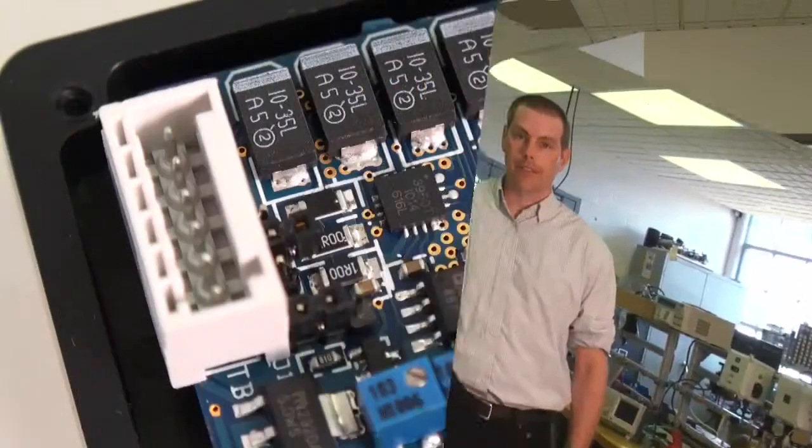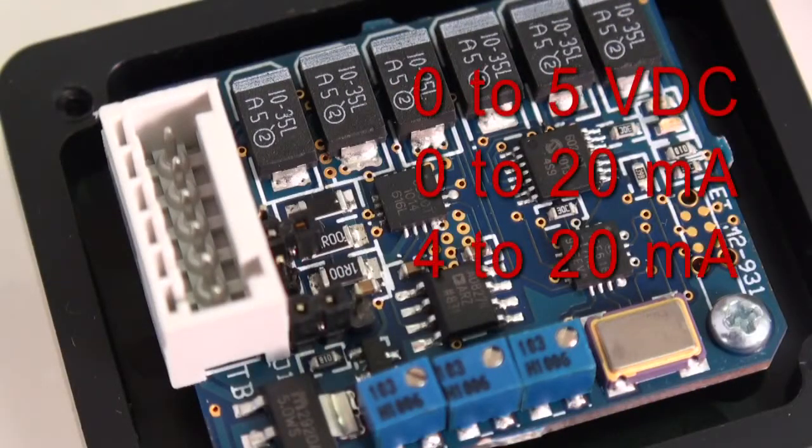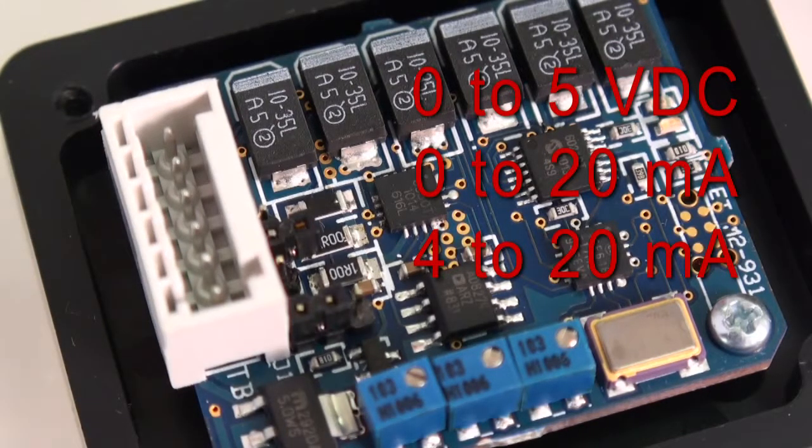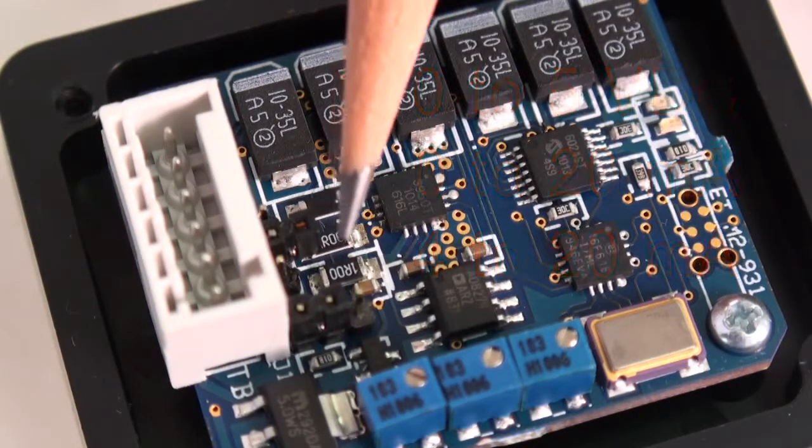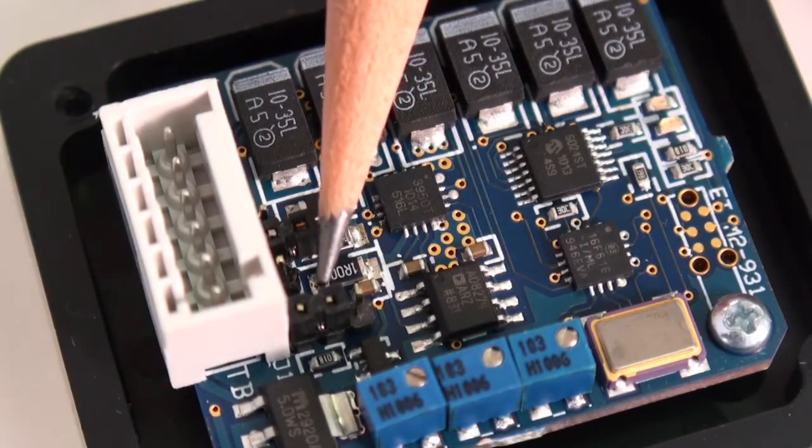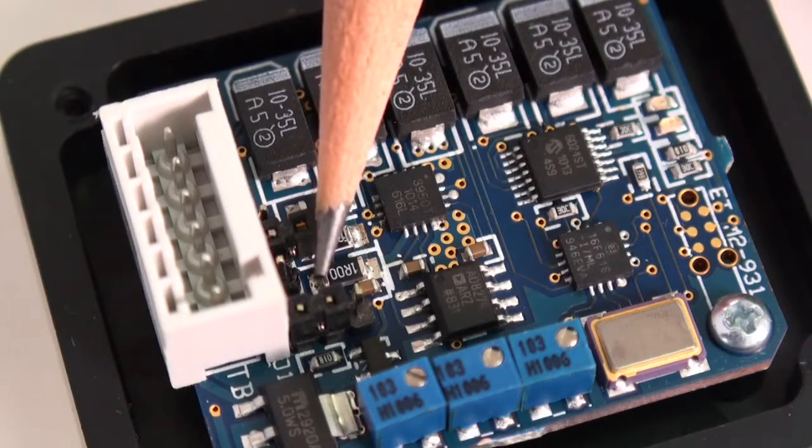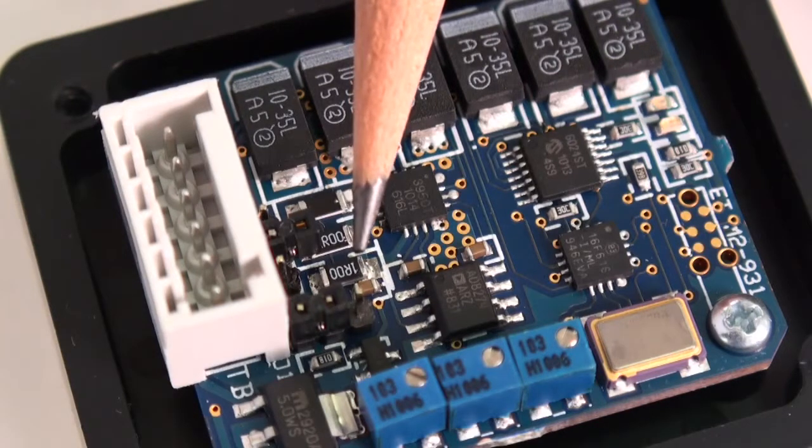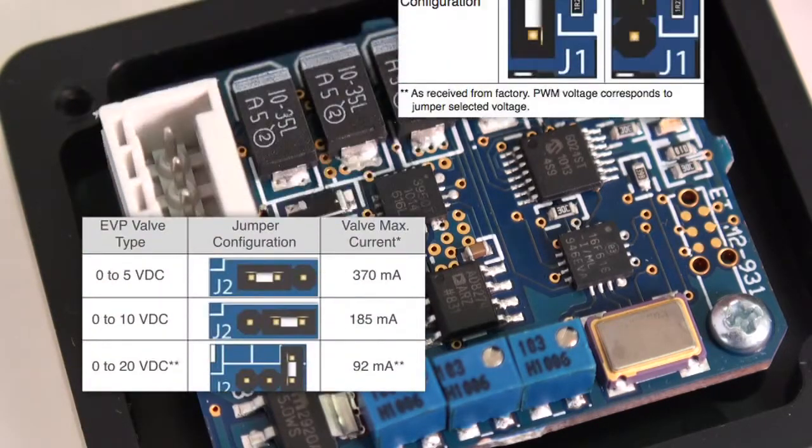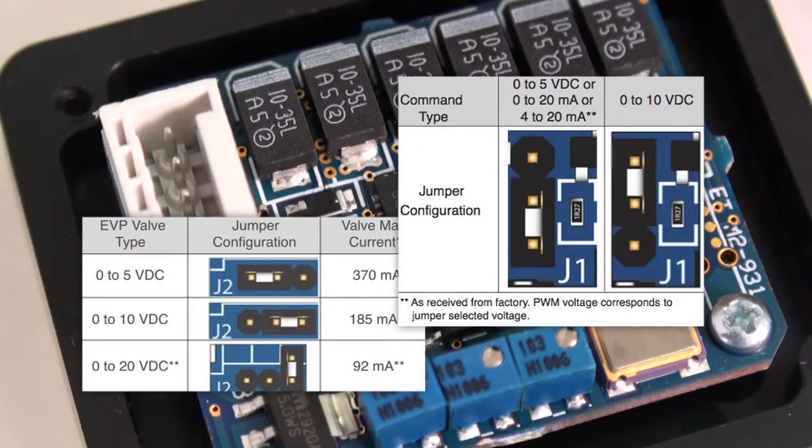And while we have the case open, let's look at the command jumper as well to see if the setting is correct for your needs. If you're using 0 to 5 volts, 0 to 20 milliamps, or 4 to 20 milliamps to control this driver, then the jumper setting for the input command signal is in the right spot from the factory. However, if you want to use 0 to 10 volts, you'll need to change that jumper. See the installation and operations manual for more information about the jumper positions.